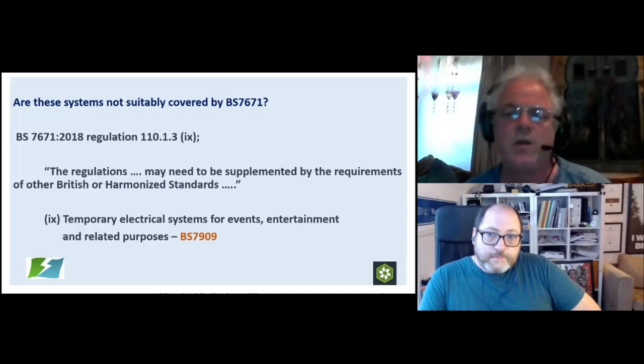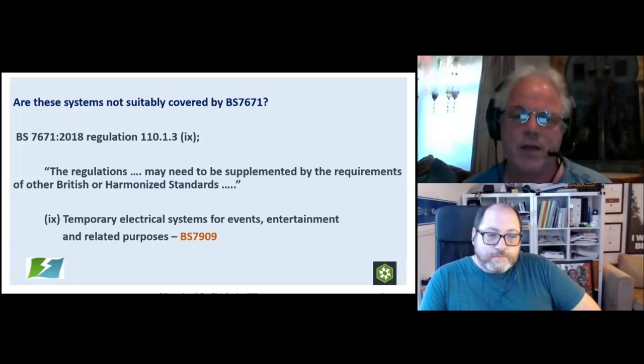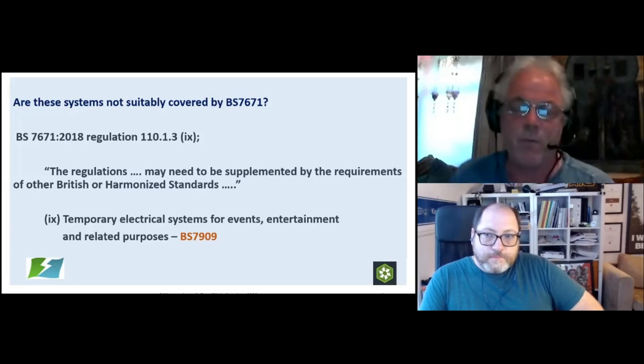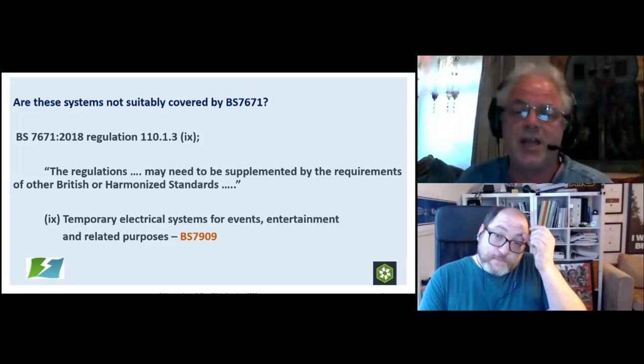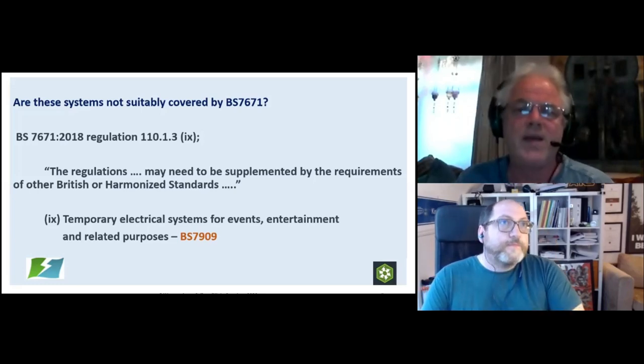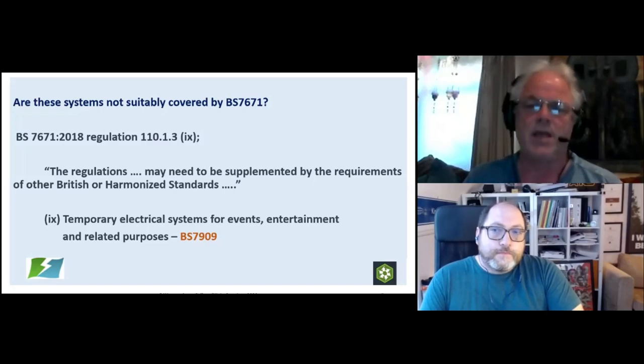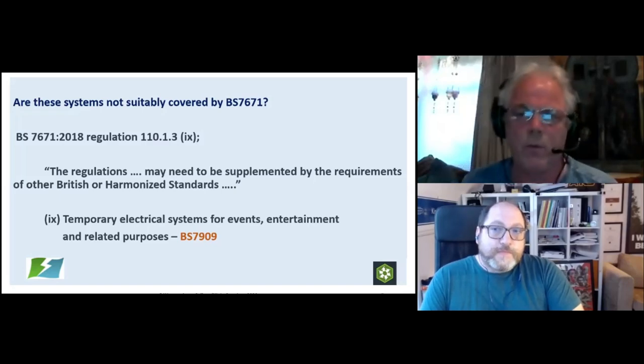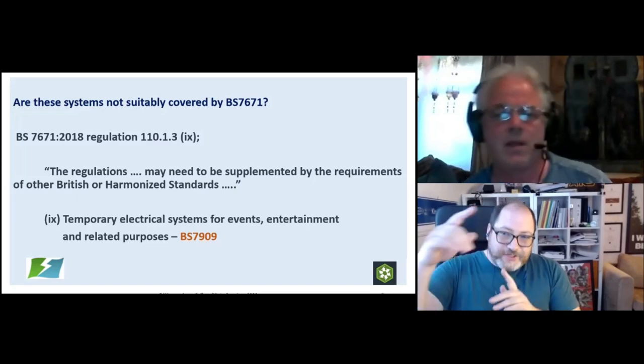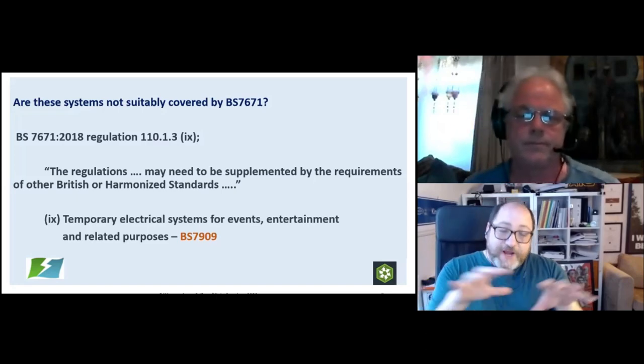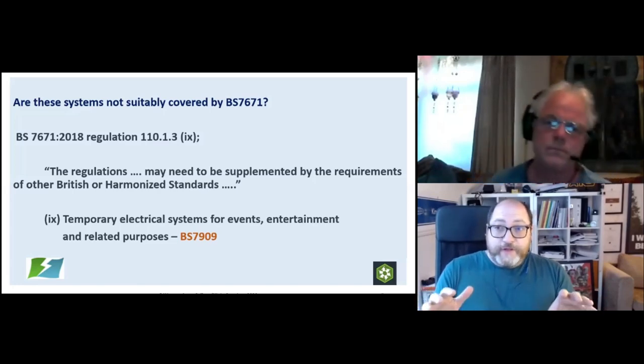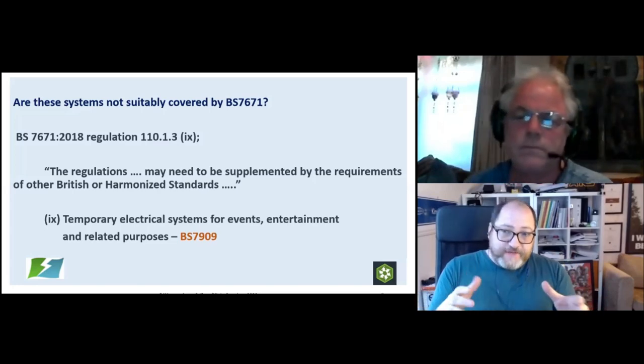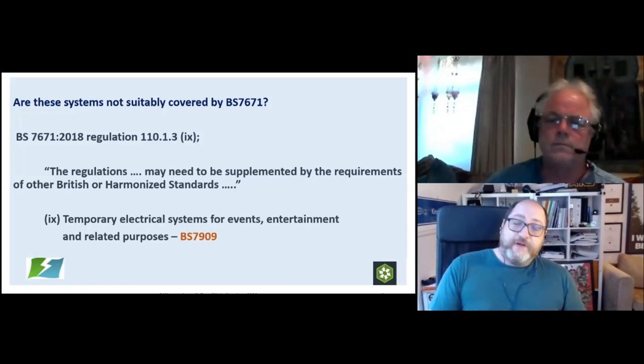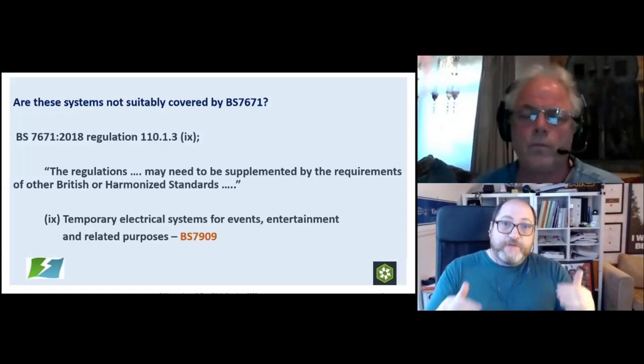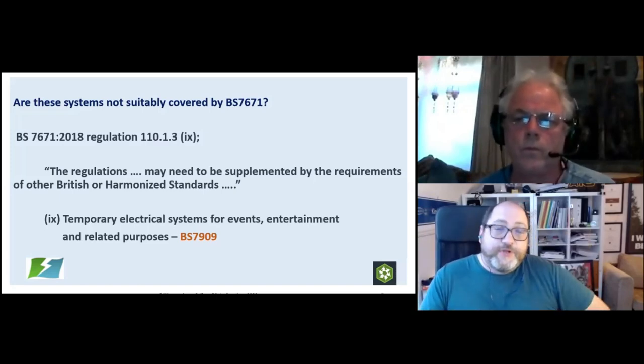But there are special situations with temporary systems where we need some additional information. Rather like in BS7671, we've got the special locations and special installations at the end in Part 7. BS7909 is the additional document to go to when we're looking at temporary electrical systems. It's the additional point when you've dried up your requirements of 7671. Anybody who goes into this area, if they just study 7909, that's not enough. 7671 is your foundation, and then 7909 has the extra supplementary requirements.